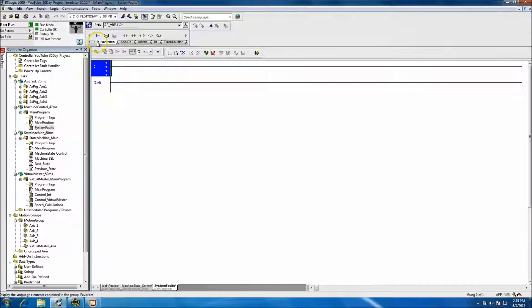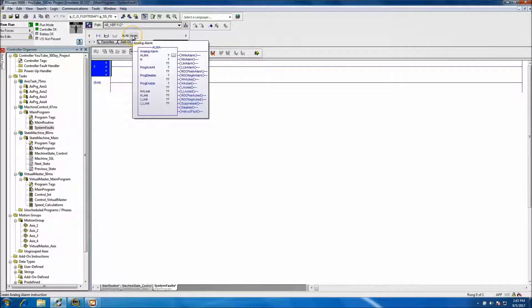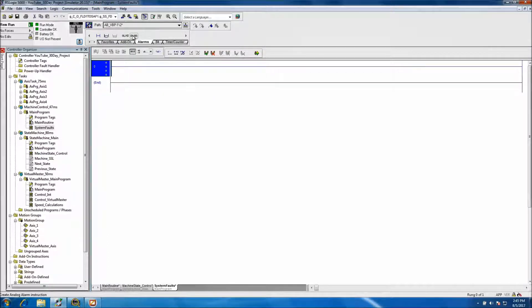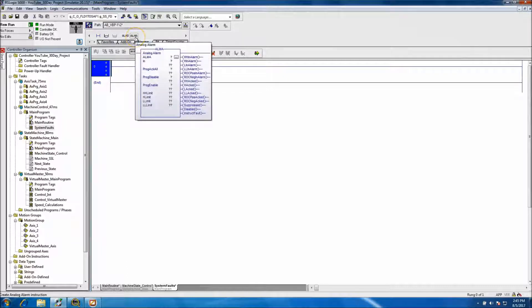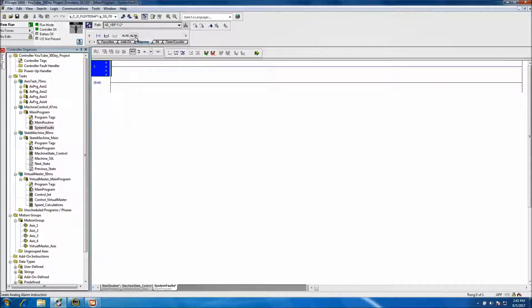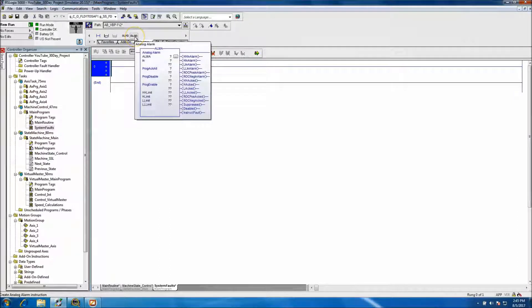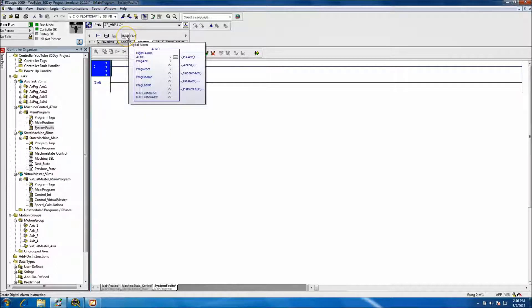If you scroll over, you have two different types of alarms: a digital alarm, which is what we will be using in this scenario, and an analog alarm. An analog alarm lets you set values — for example, if it's below 4 milliamps create an alarm, or if it's getting below 8 milliamps create a warning. We won't be digging into that; what I'd like to do is focus on ALMDs.